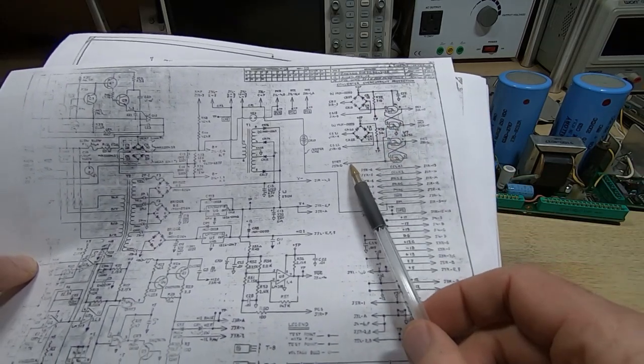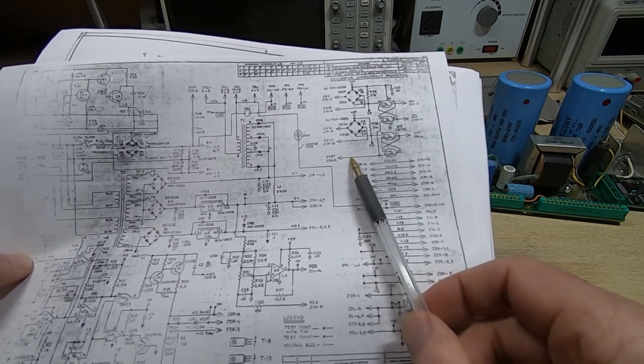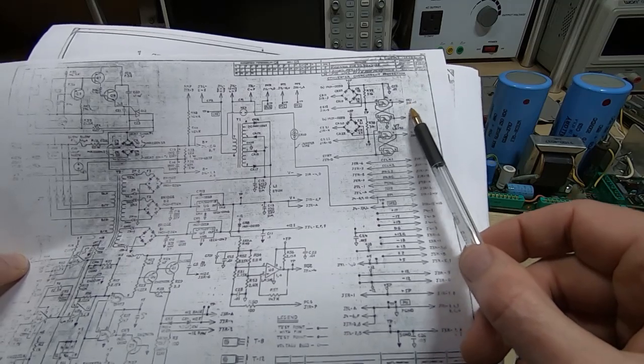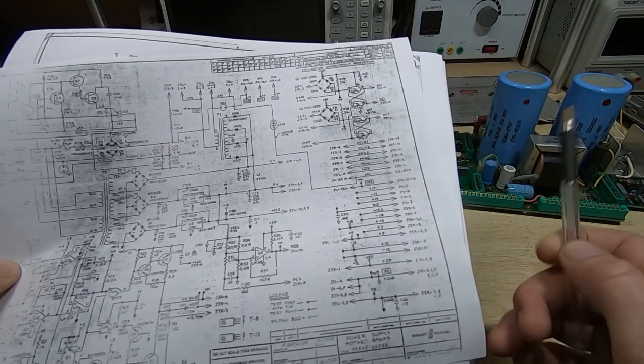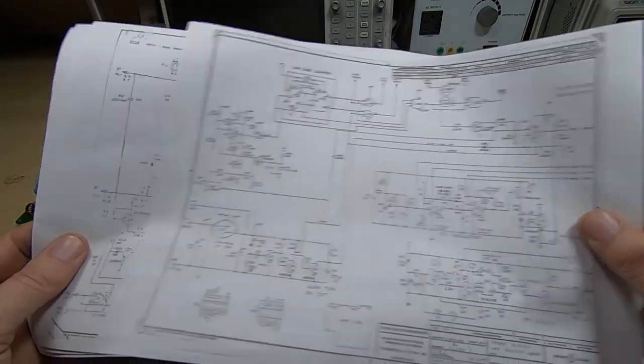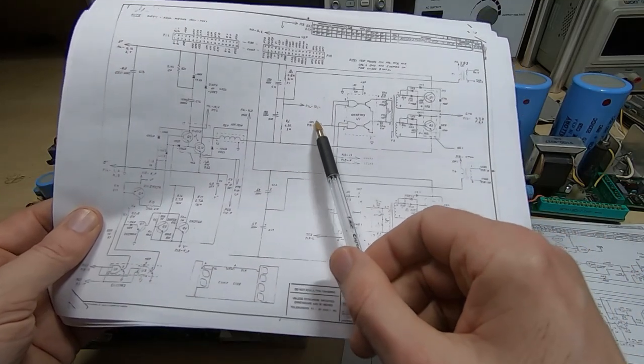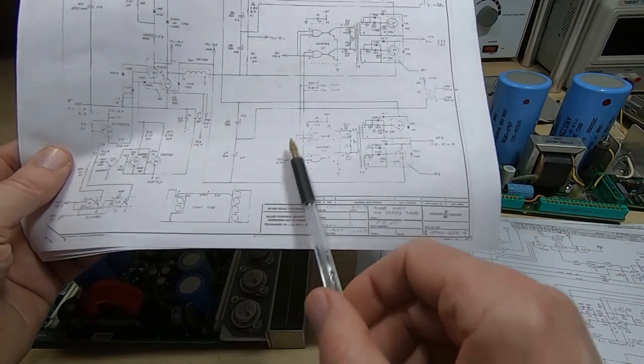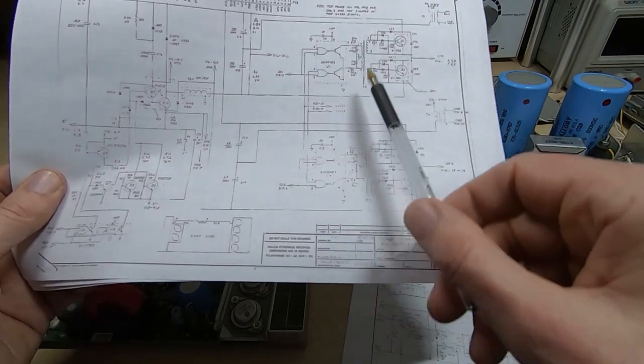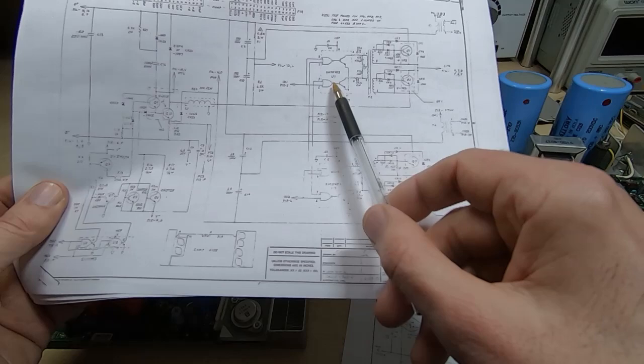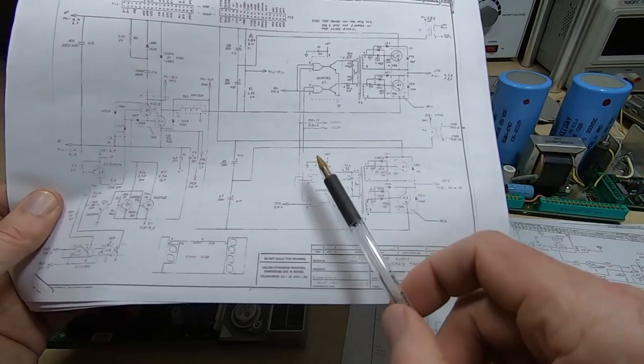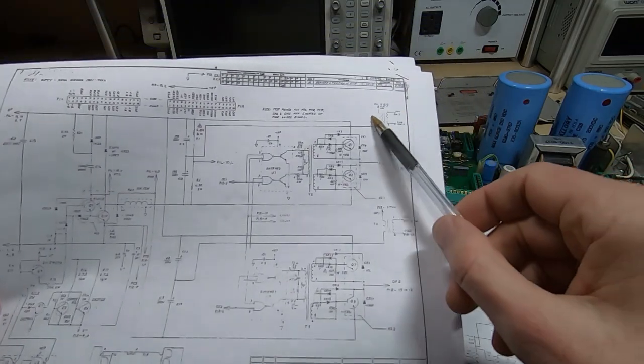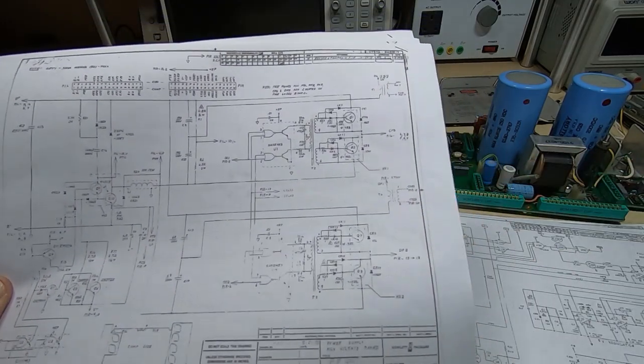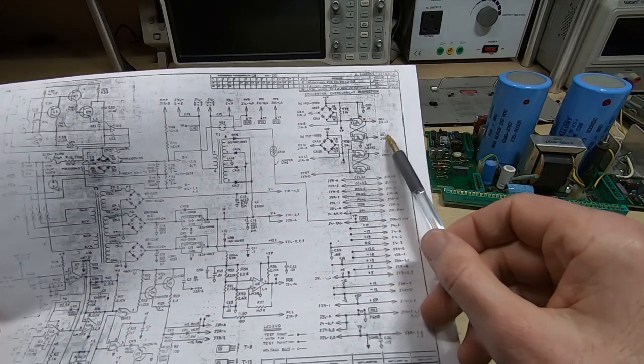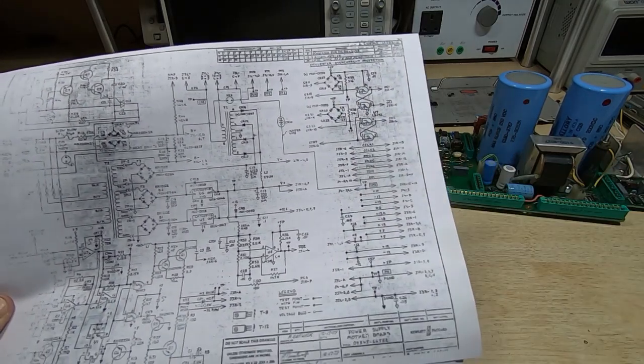These latches are set when the power supply is first switched on, and it effectively enables the choppers. We have OC1 and OC2, used to control the chopper circuit. So if we look here, we have OC1, down here we have OC2, and these enable or disable the chopping circuits. The latches we just looked at enable these circuits, and if we get an overcurrent event because the current through this transformer is too high, it causes the latches to reset, and that shuts down the chopping circuits. That's the overcurrent protection for the system.